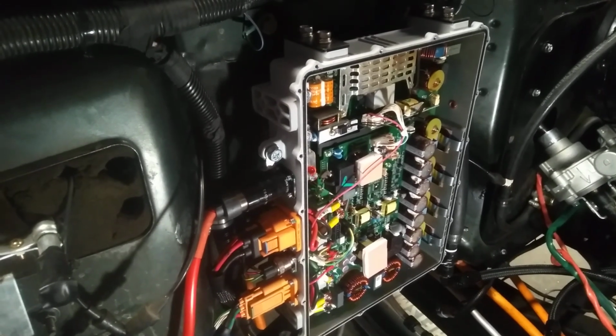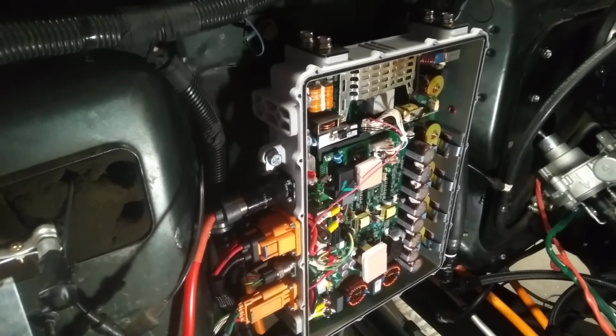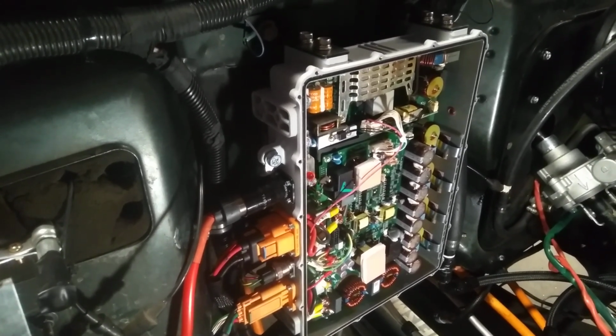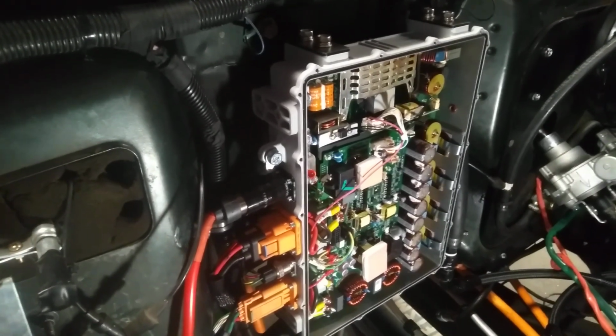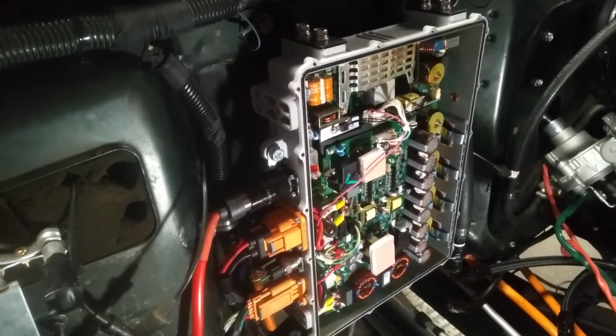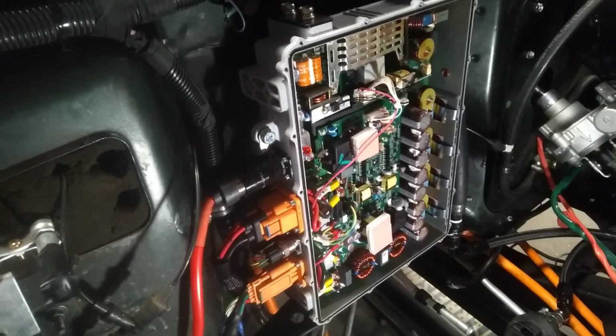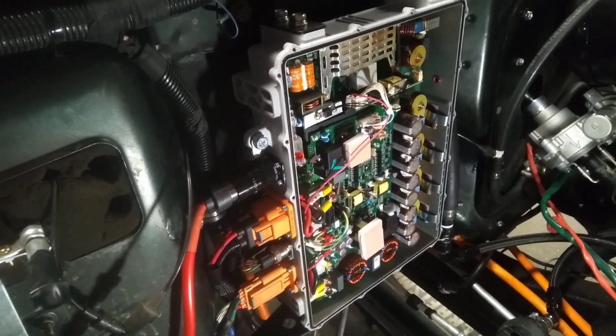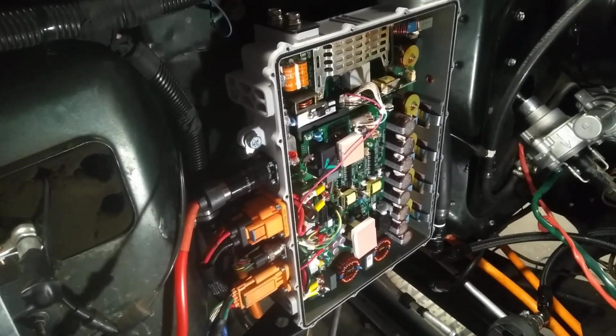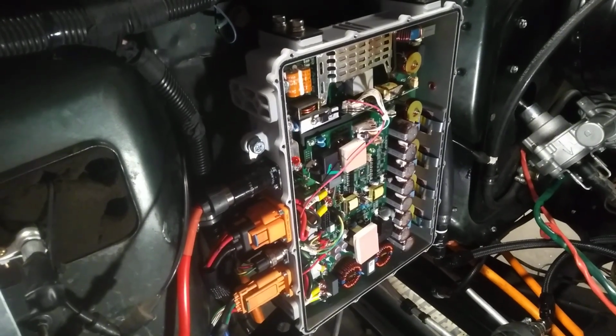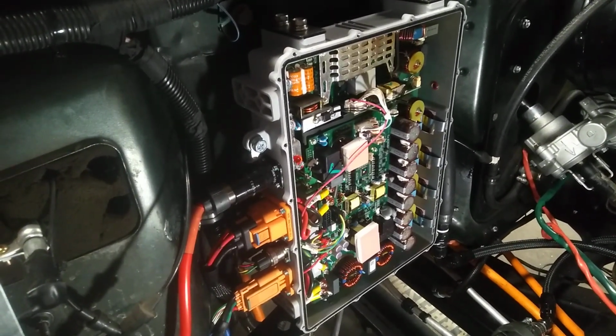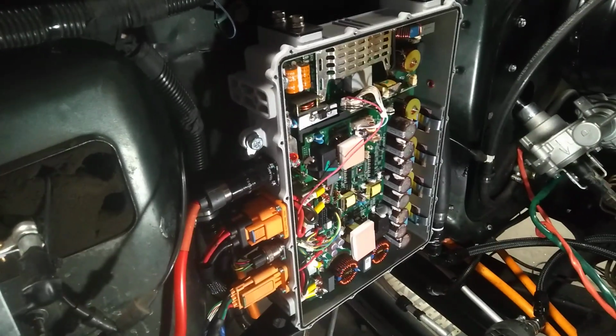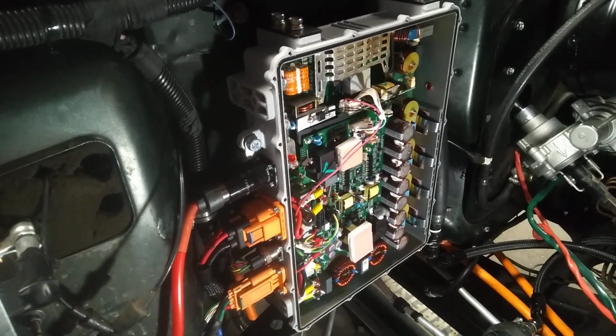So that's why my contactor welded shut, because it was opening and closing under a really high load, charging up those capacitors. And it's ultimately why this thing, the Stealth one, failed, because those capacitors were charging too fast. So that's why you have a pre-charge circuit, to avoid that from happening.